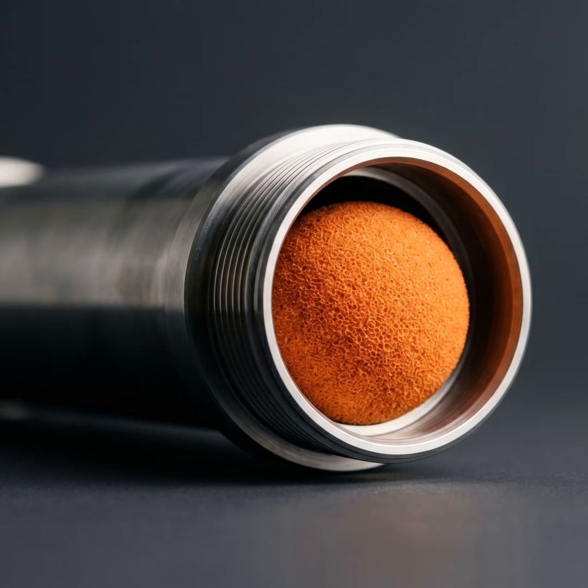That makes total sense. So what does the chiller's computer system do when it senses the water isn't getting cold fast enough? It ramps up. It has to work harder. It just brute forces it. Right. The compressor is forced to draw immense, sometimes staggering electrical loads just to brute force the heat transfer through that barrier of mineral scale. You know, the sources drop a statistic that honestly made me pause. I had to reread it just to be sure I saw the numbers correctly. The energy consumption stat. Yeah. They note that chillers can consume up to 60% of a commercial building's total electrical energy. It's unbelievable, isn't it? 60%.